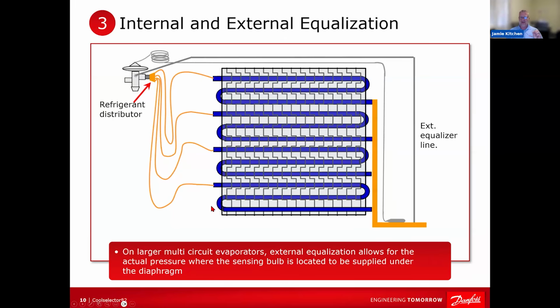If you have a distributor, now you've got a whole set of differences here. Almost all air conditioning that I've ever seen, at least that I remember, has a multi-circuited coil for efficiency. Larger refrigeration systems have a multi-circuited evaporator. Don't think just because you have a piston or a cap tube that it's single circuit. It's not, right? Remember all the old piston air conditioning systems out there? There's still some of them there.